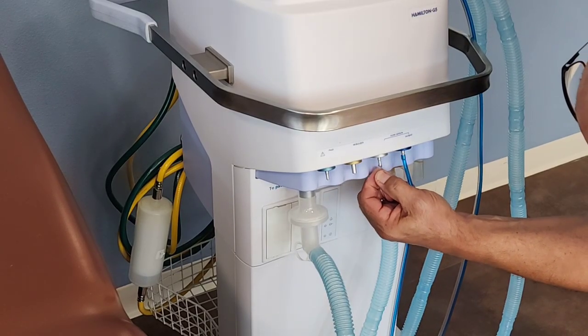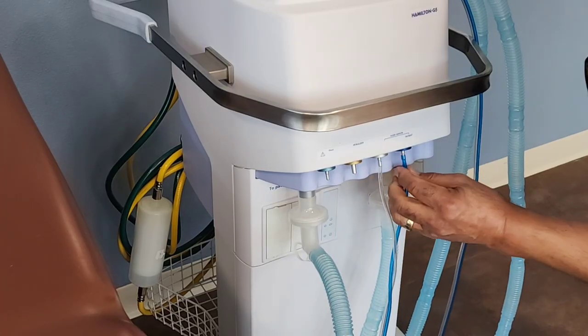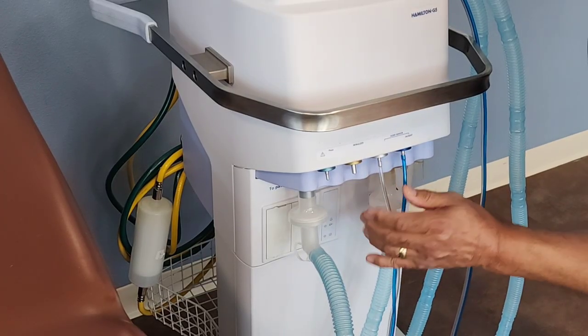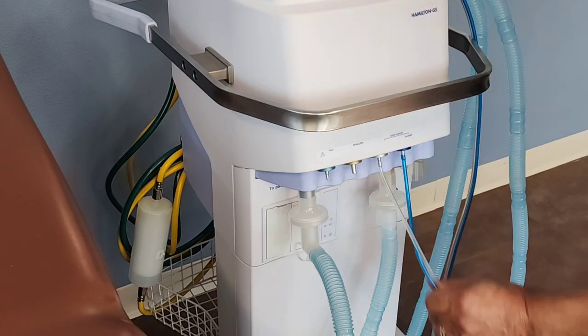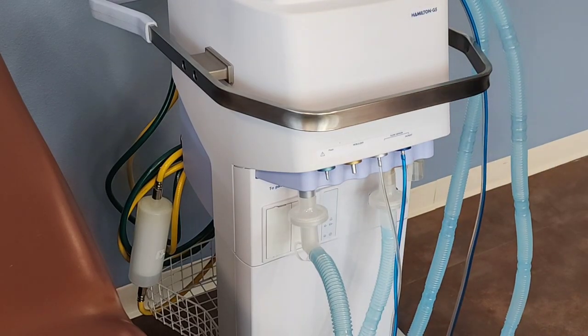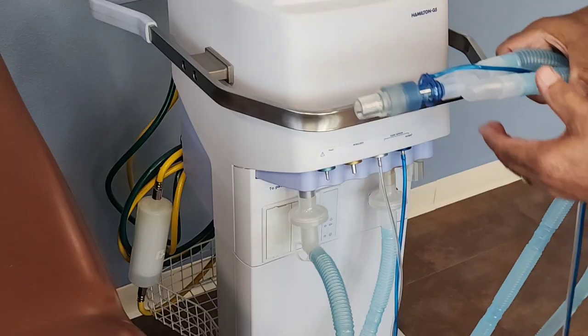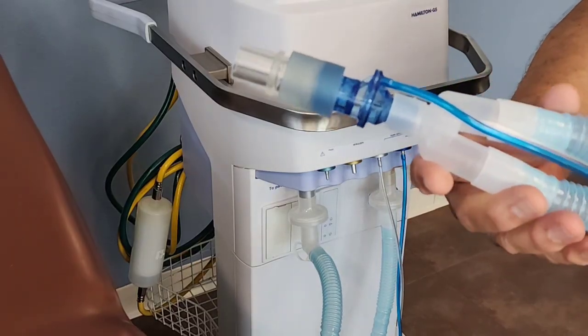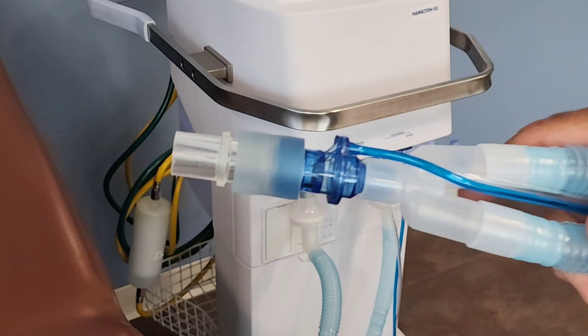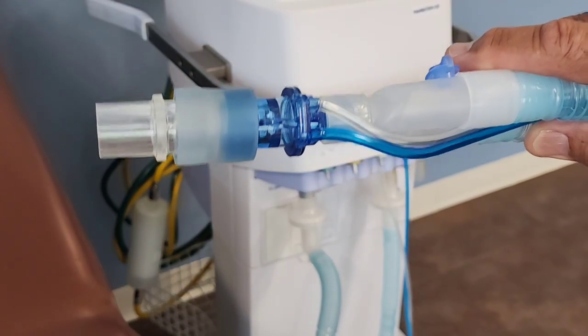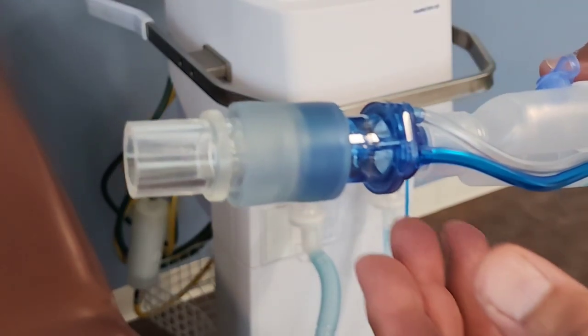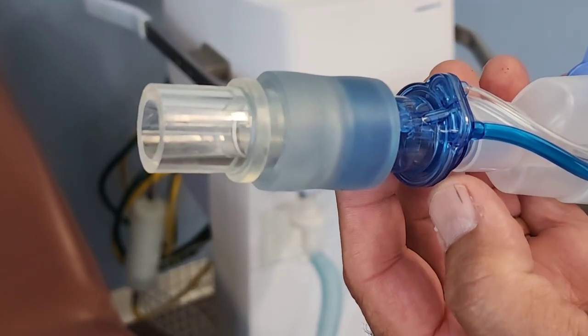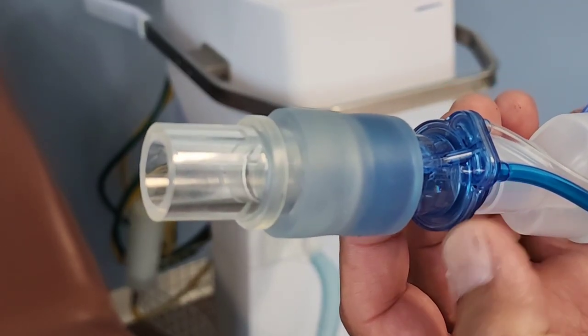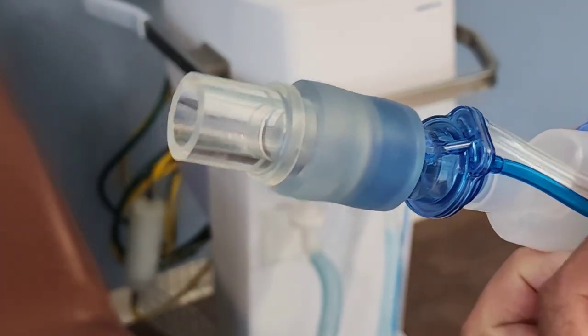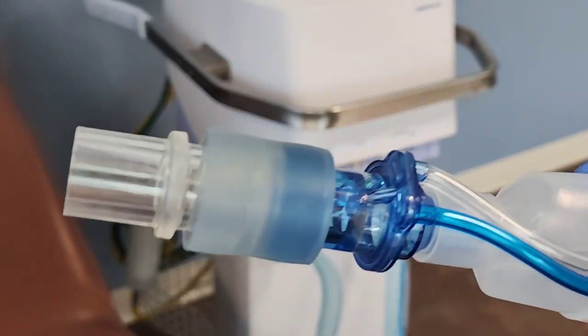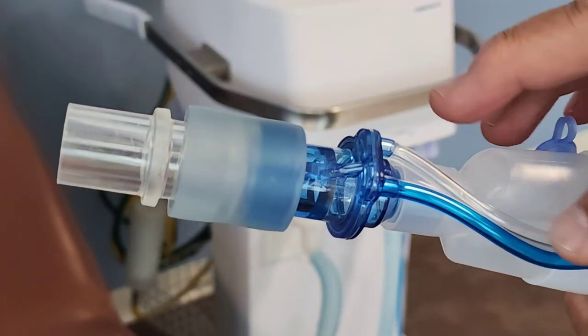The flow sensor on this one doesn't work. There's a calibration error, and it might sense tidal volume a little bit differently, but we're not able to do any maintenance on this one. But anyhow, this is what the flow sensor looks like. Let's see if you're able to see it. Okay, be very careful with this. These are not easy to find. Sometimes right in the center here it could crack, but this one's a new one, so just be really careful.